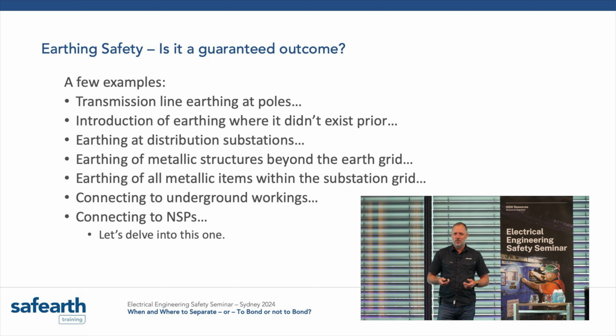If it's too hard, then assess it and risk it and look for an exemption, just like some of the other speakers have been talking about, needing exemptions for certain things. You can absolutely do that. If there's no foreseeable risk of direct or indirect energisation and there's no touch voltage hazard at that thing, then don't earth it. You might make it worse by earthing it.